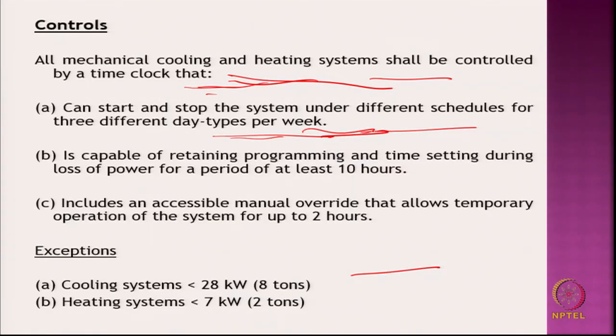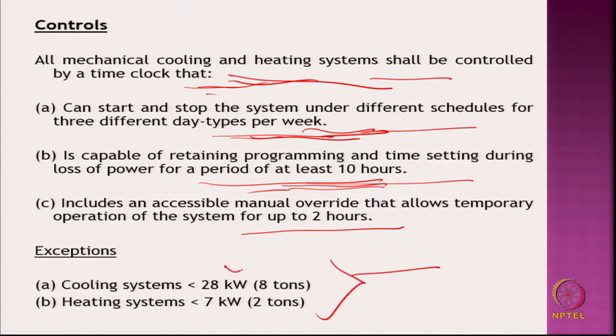According to the schedule it should operate, and it should be capable of retaining the program even if there is a power failure for at least 10 hours, and a manual override has to be there. This is of course not required if you have a cooling system that consumes less than 28 kilowatt or 8 tons, and a heating system of 2 tons; it is not required.